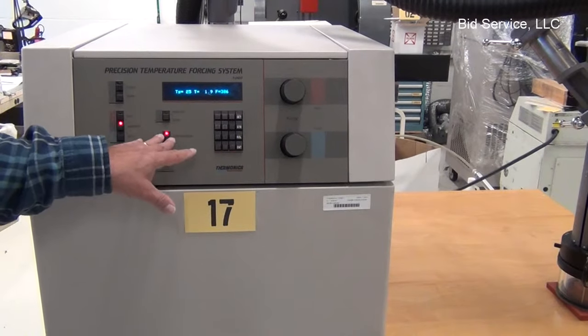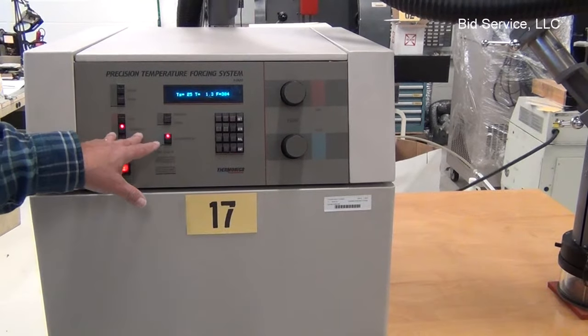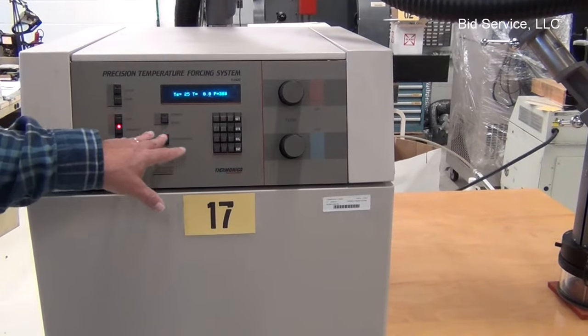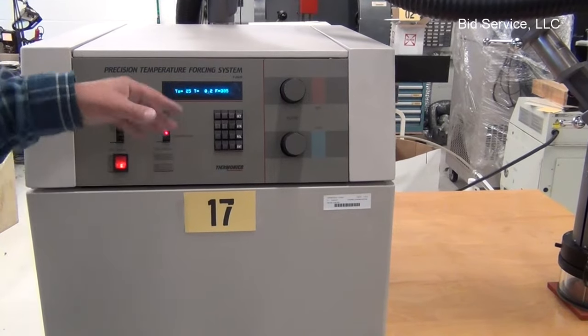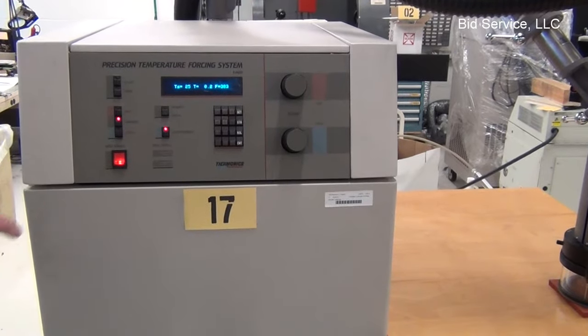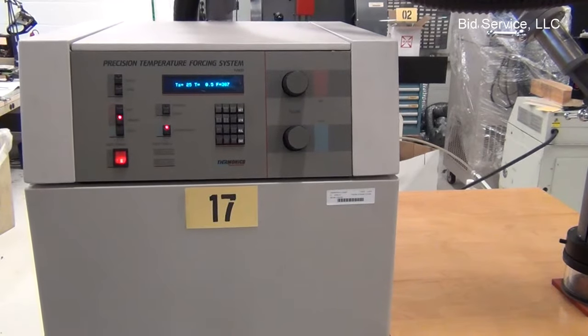The compressor, you want to go through a dry-out procedure for about five to ten minutes, and then turn the compressor on. That takes about twenty minutes to cycle and get ready to cool.